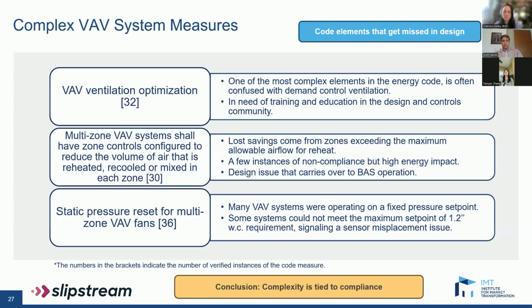The next measure we have here is that multi-zone VAV systems shall have zone controls configured to reduce the volume of air that is reheated, recooled, or mixed in each zone. This is also a high impact measure in the sense that even though there weren't as many projects that did not comply, it still resulted in a lot of lost savings, to the point where I ranked this measure to be among the top 5. Lost savings here come from zones exceeding the maximum allowable airflow for reheat at the terminal boxes. In a few instances where we observed noncompliance, it seems to be an issue that originated at the design stage and then got carried over to operation.